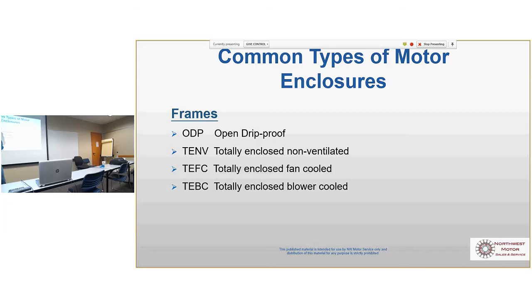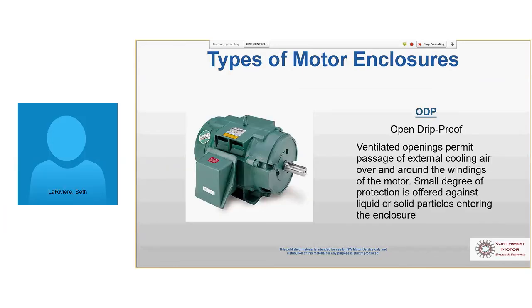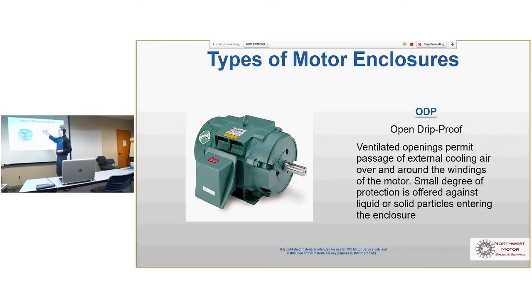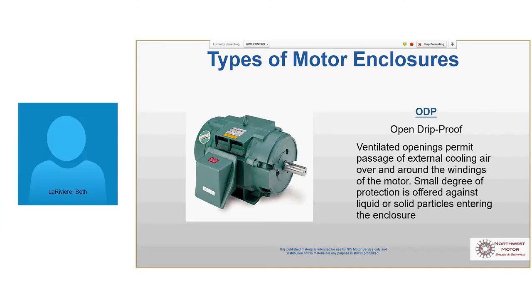Picture of an ODP here. So this one has vents on top. So what NEMA says, if it's an ODP, water coming in at less than a 15 degree angle from vertical won't get in there. So if this water's coming in more or less straight down, it won't get in there. Up to 15 degrees, it won't get in there. If the water's coming in at 90 degrees, it would get in there. Not a good application for an open drip proof.